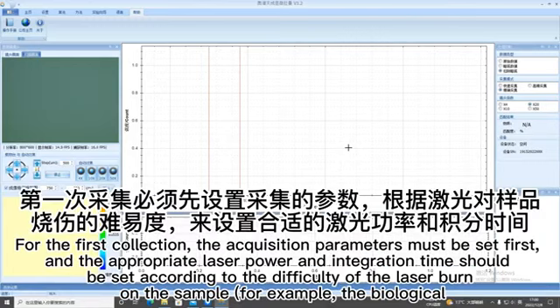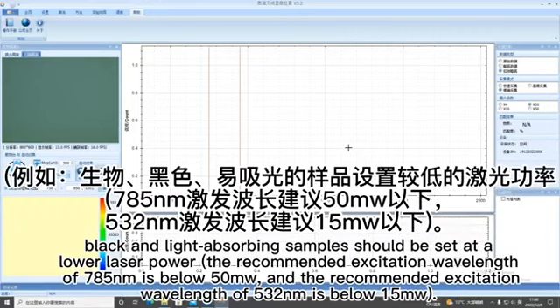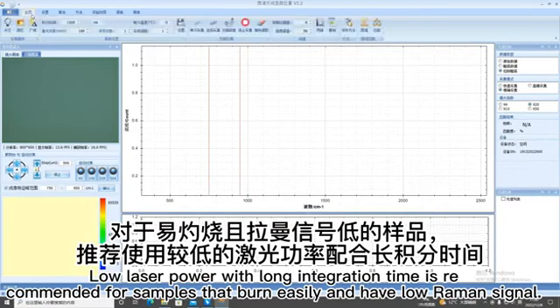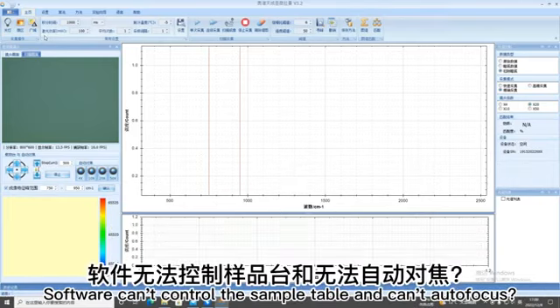For the first collection, the acquisition parameters must be set first, and the appropriate laser power and integration time should be set according to the difficulty of the laser burn on the sample. For example, biological, black and light absorbing samples should be set at a lower laser power. The recommended excitation wavelength of 785 nm is below 50 mW, and the recommended excitation wavelength of 532 nm is below 15 mW. Low laser power with long integration time is recommended for samples that burn easily and have low Raman signal. Software can't control the sample table and can't autofocus.